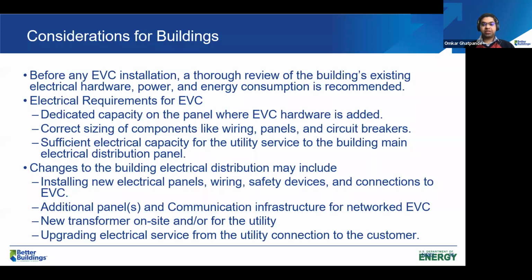Many commercial buildings currently have limited additional capacity for adding this charging equipment and would require significant infrastructure changes to accommodate them. Some of these changes might be panel changes, additional wiring, circuit breakers, and an evaluation of the utility service main coming to the building.